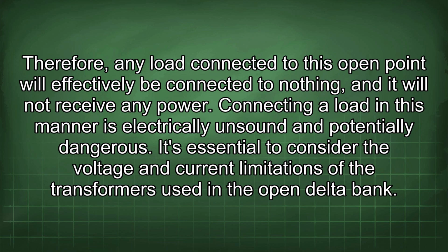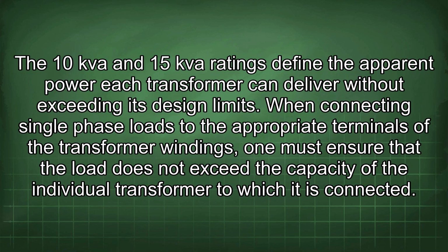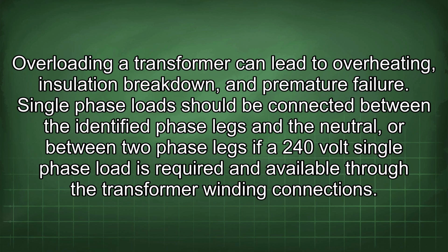It's essential to consider the voltage and current limitations of the transformers used in the open delta bank. The 10 kVA and 15 kVA ratings define the apparent power each transformer can deliver without exceeding its design limit. When connecting single-phase loads to the appropriate terminals of the transformer windings, one must ensure that the load does not exceed the capacity of the individual transformer to which it is connected. Overloading a transformer can lead to overheating, insulation breakdown, and premature failure.